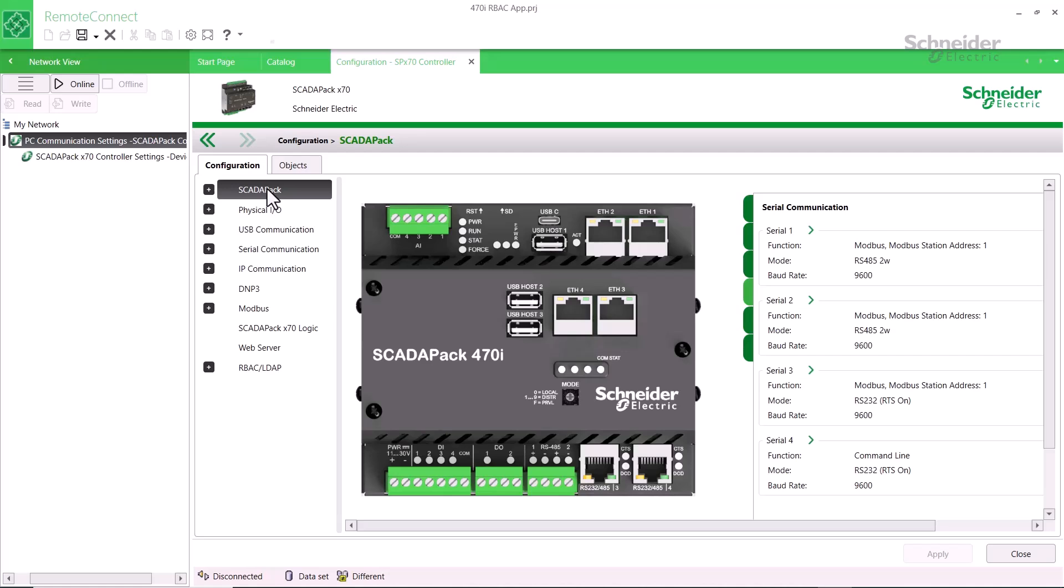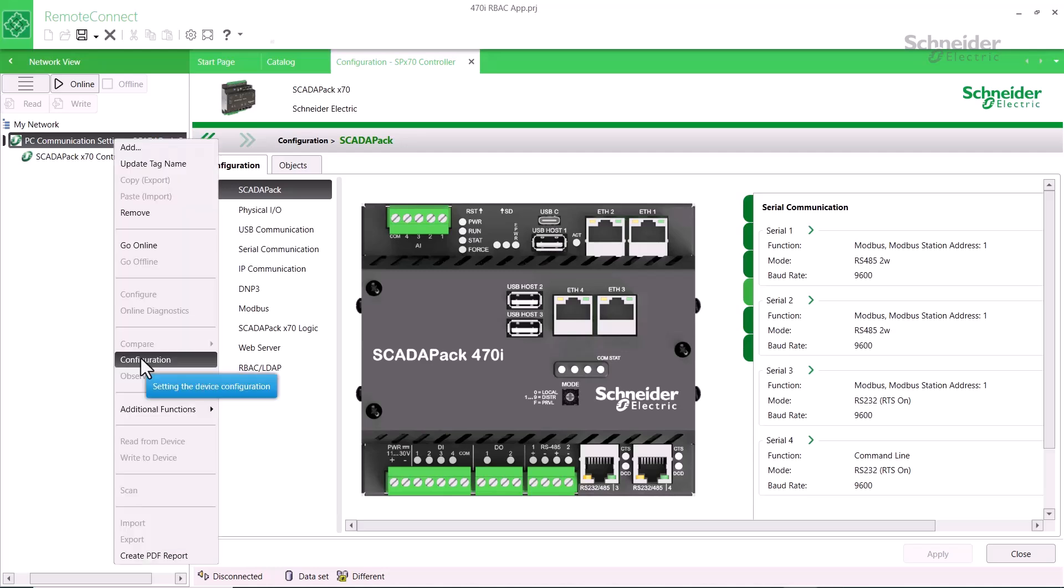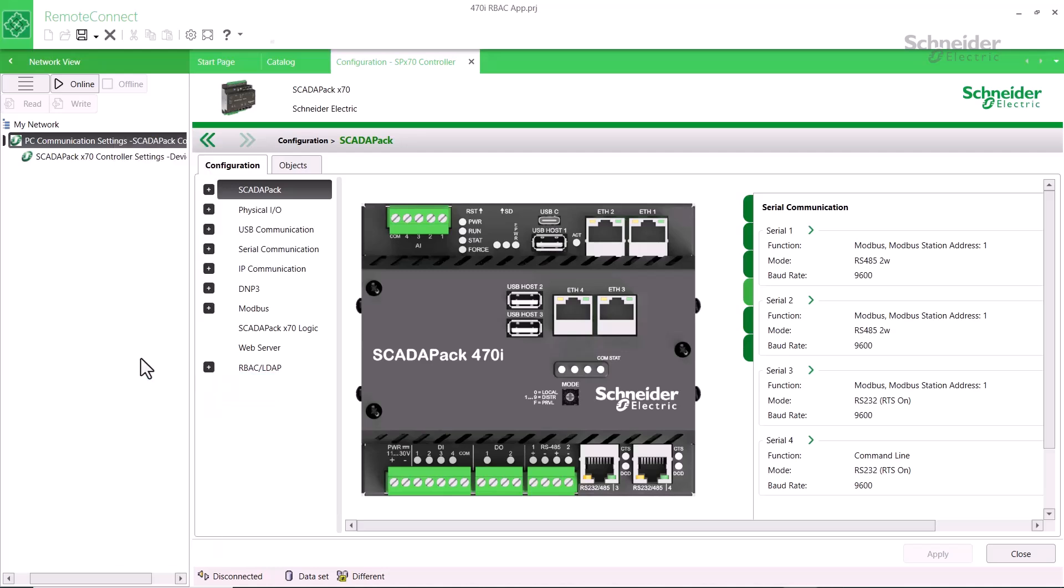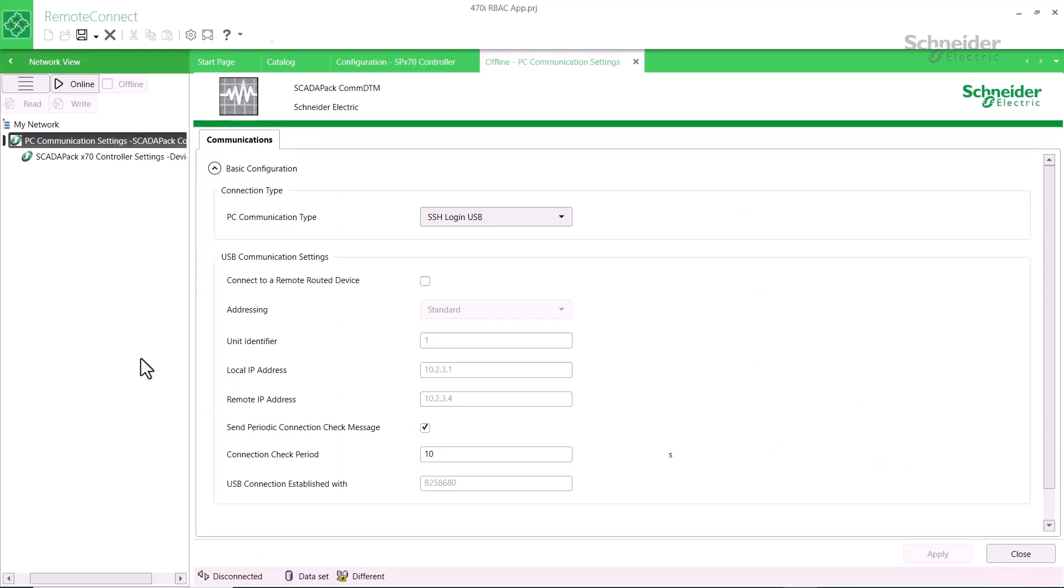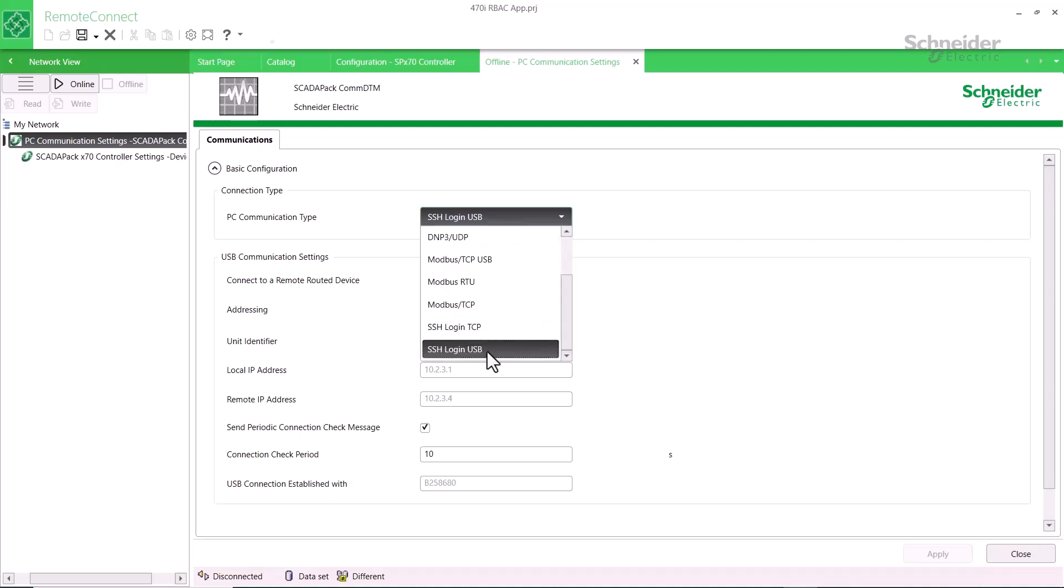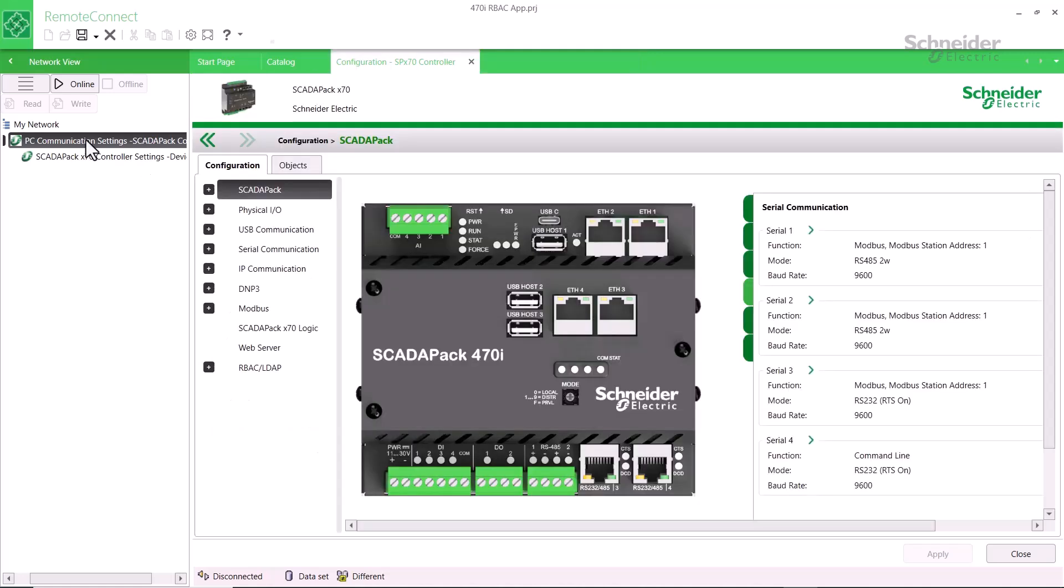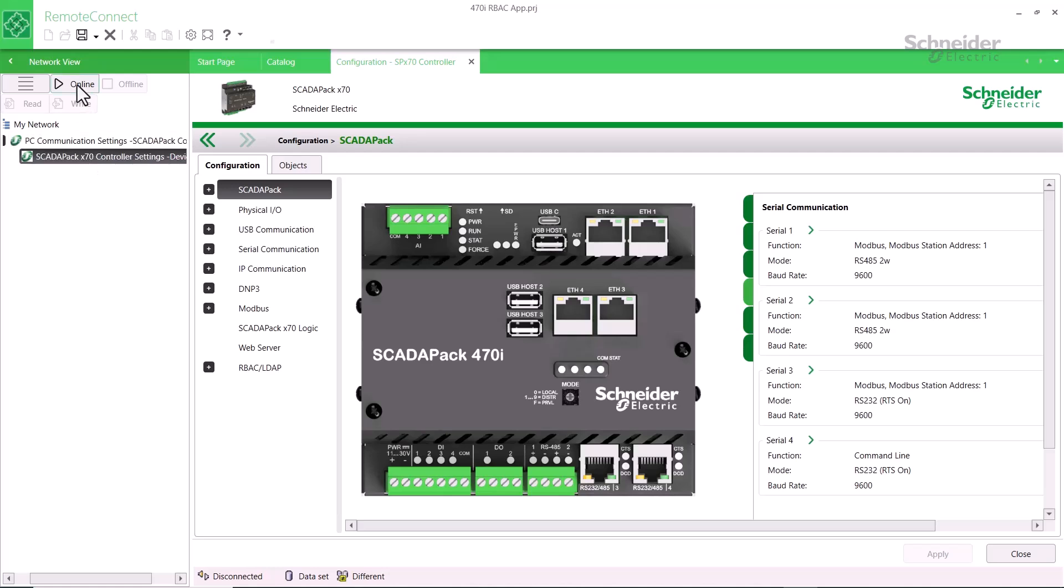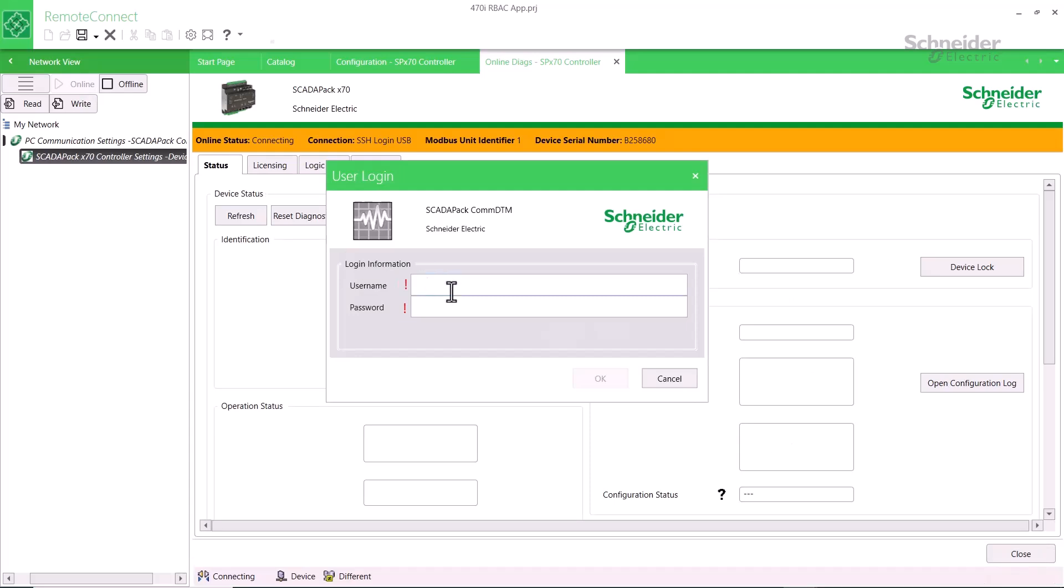To log in to Remote Connect with RBAC-enabled, right-click on the PC communication settings in My Network and select Configuration. Then choose either SSH Login USB or SSH Login TCP. After you close the Communication Configuration dialog, select SCADAPack X70 Controller Settings and click the Online button. The User Login dialog then appears. Enter your username and password, then click OK.